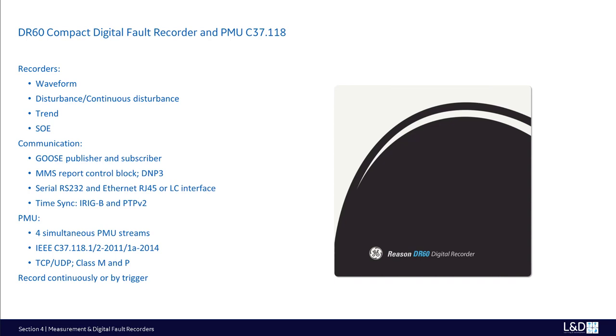The DR60 provides a powerful and cost-effective synchrophasor measurement solution according to IEEE C37.118 2011 to 2014 standards and is capable of transmitting synchrophasor in up to 4 separate data streams. Each stream can be configured independently based on contents, frame rate, performance class P or M, and communication modules TCP or UDP.